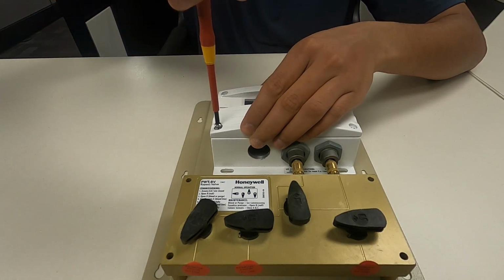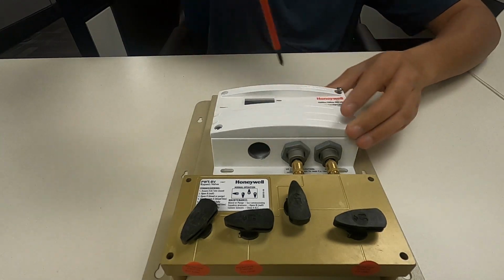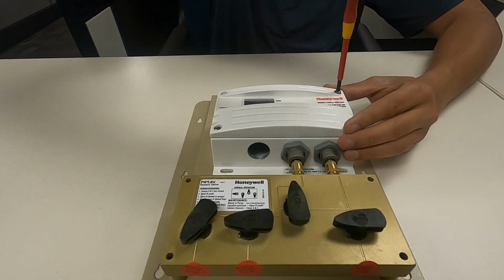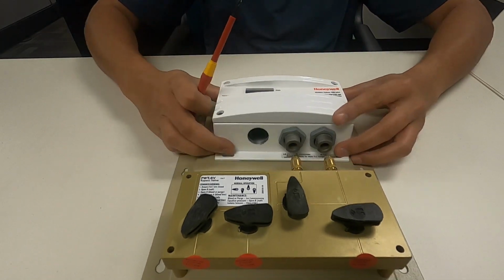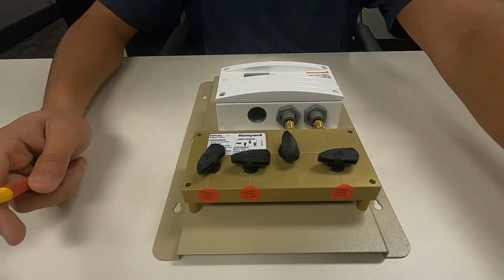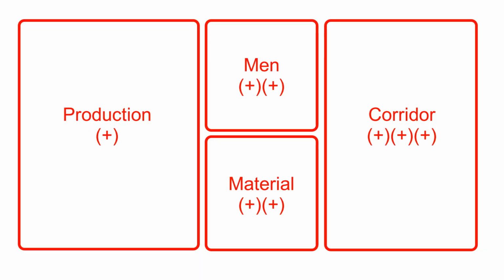The wall-mounted pressure sensors are very critical in pharmaceutical applications. Basically, pharmaceutical facilities need a positively pressurized corridor, a less pressurized material or men room, and even lesser pressurized production areas. The reason for this is that production areas won't have the same product in adjacent areas. To avoid blending two products and to contain the product within the area, pressurization is very critical. Temperature and humidity also play an important role in production. Specific products need specific requirements of temperature and humidity with utmost precision.